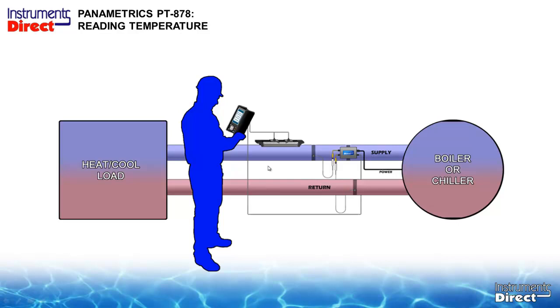But remember, you've got to collect all those data points. So in this case, flow is 1, temperature over here is 2, another temperature over there is 3, and then we calculate the BTU. So you're eating up your data points really quick.